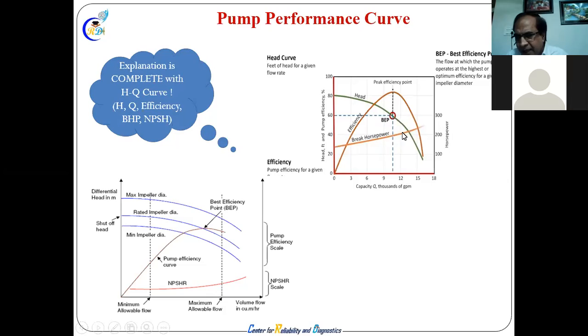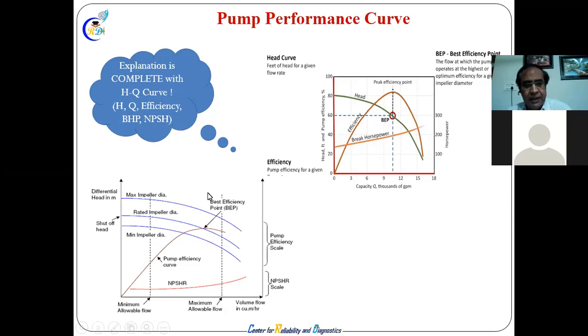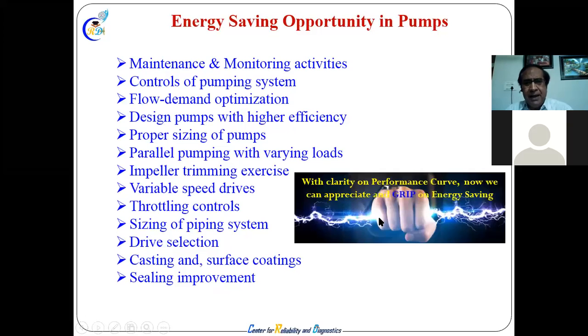If you go here, energy is more, but your pressure requirement is less. If you want more pressure, energy is less, but your flow will be low. So judicious judgment should be done. How the impeller diameter changes efficiency over time is shown in this graph. Okay, and that means for energy saving in pumps, there are a lot of possibilities.